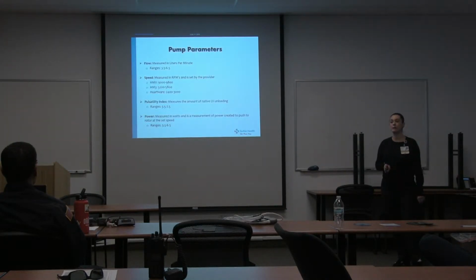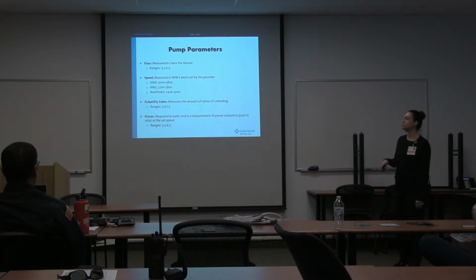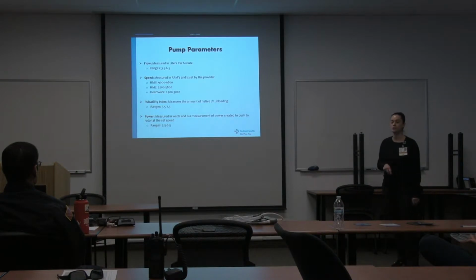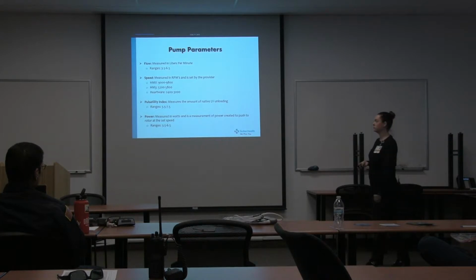So pump parameters. The different pumps have controllers, which I showed you, that are attached to the patient 100% of the time. Those controllers have calculations that they provide for the patient's pump inside the body to give you an idea of what's happening to that pump and the blood flow in the patient's body.